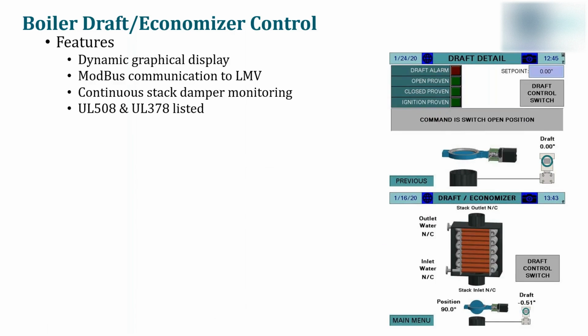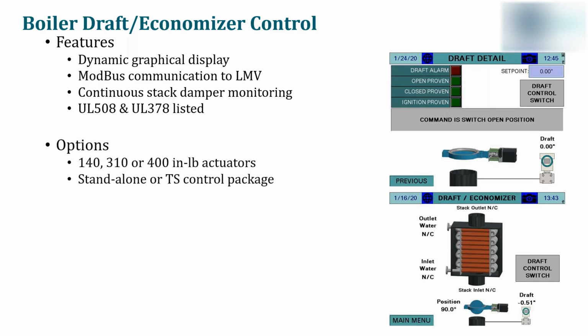Now, the features of this system are, it has a dynamic graphical display. The dynamic graphical display for stack draft pressures provides operators with a visual aid for operational monitoring. It also has Modbus communication to LMV, which helps minimize the amount of field wiring. It has continuous stack damper monitoring, and it is UL 508 and UL 378 listed. Options include 140, 310, and 400 inch-pound actuators. And you could also get this as a standalone system or as part of a touchscreen control package.